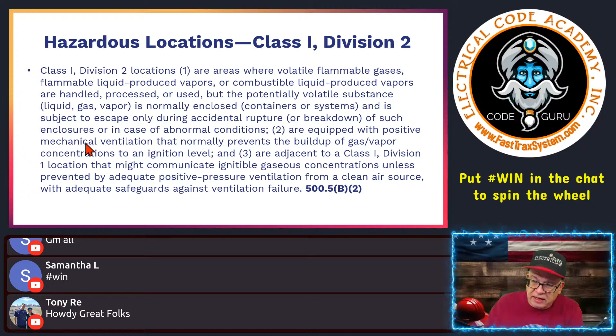Number 2, are equipped with positive mechanical ventilation that normally prevents the buildup of gas vapor concentrations to ignition levels. In other words, it could be in a location where it has a system in place with positive mechanical ventilation. So once the pressure gets to a certain level, it mechanically ventilates to keep it below certain thresholds. That area would be a Class 1 Division 2 location because of that mechanism.